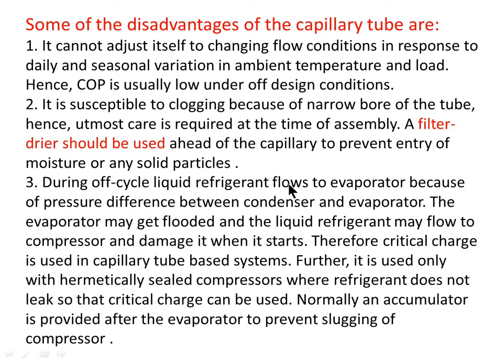During the off cycle, liquid refrigerant flows to the evaporator due to the pressure difference between condenser and evaporator. The evaporator may get flooded and liquid refrigerant may flow to the compressor and damage it when it starts. Therefore, a critical charge is used in capillary tube-based systems, and it is used only with hermetically sealed compressors where refrigerant does not leak. Normally an accumulator is provided after the evaporator to prevent slugging of the compressor.